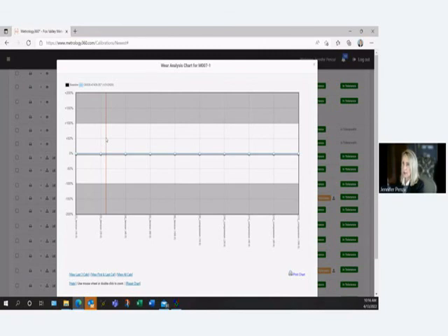What you're seeing here is a window of tolerance. Everything in white is in tolerance. Anything in gray is out of tolerance. As you can see, this particular force gauge was dead on, right in tolerance. If it had in any way drifted out, it would show that line going up.